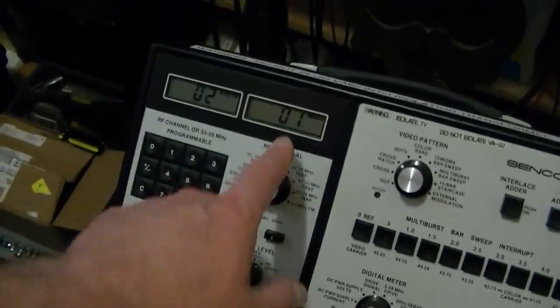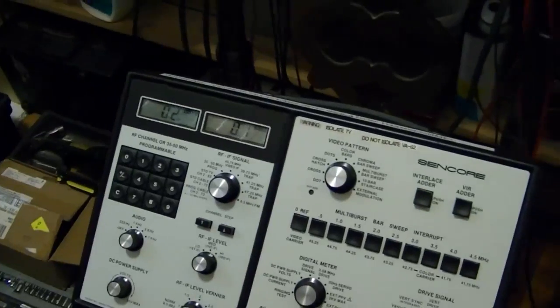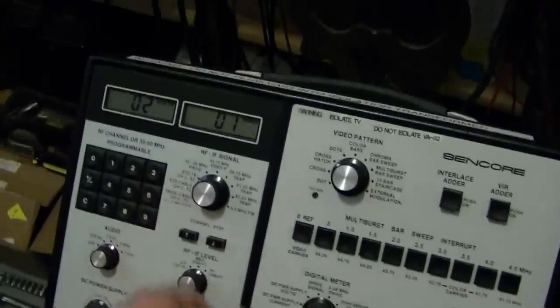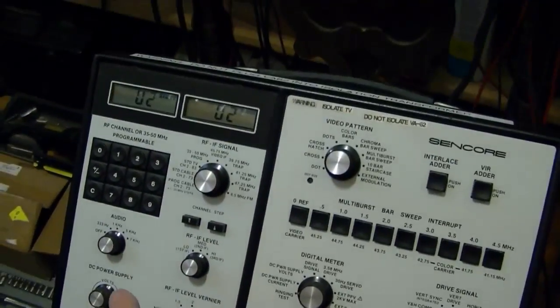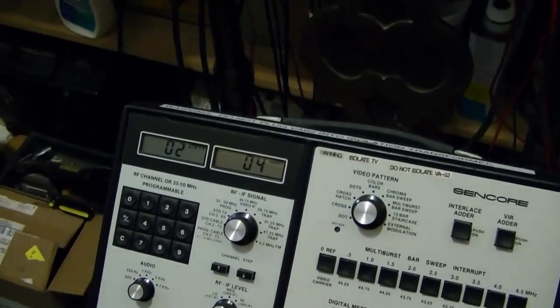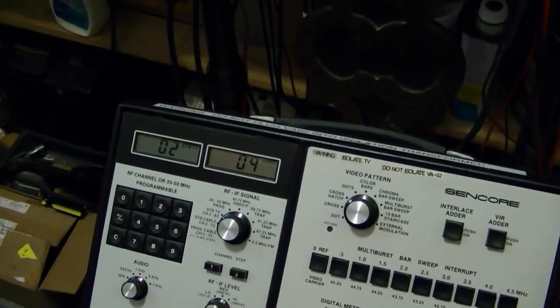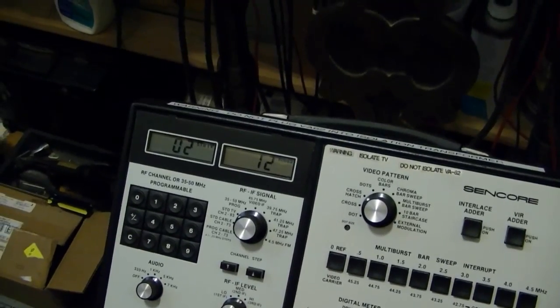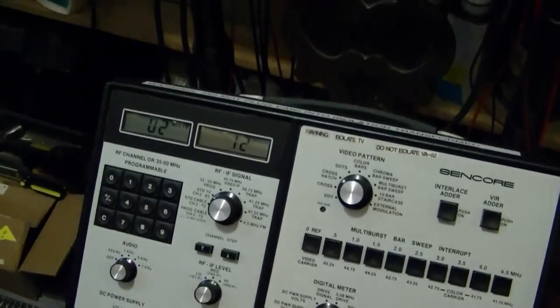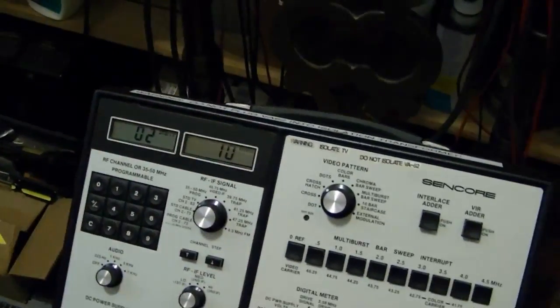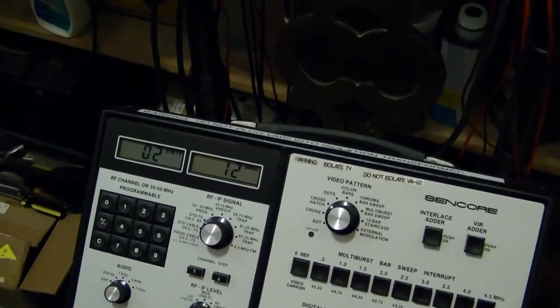So in this position we've only got one ring, no good. They say if you get 10 or better, it's good, done, that's all you need to test — no need to check any other windings. If between these two leads it's good, they say it's good. So here we got one ring. And we've got 2, 4, 9, 12 — hey, it's a good flyback. And here we get 10. But as I say, 10 or above, in any position, it's good.